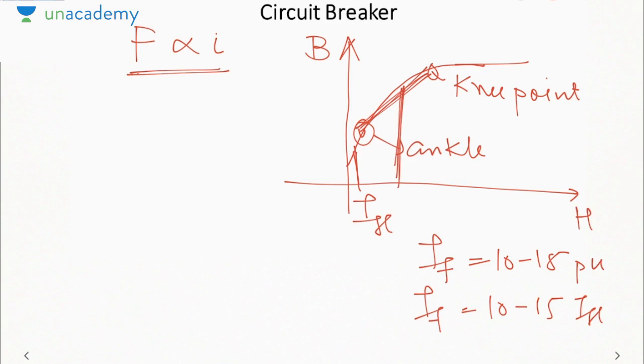So normally we operate below the ankle point or at the ankle point, so that as soon as I get a fault, or as soon as the current becomes high, I will end up in the linear region, so that the operating force is proportional to the current. That is how the circuit breaker must be, that is how the current transformer must be designed.